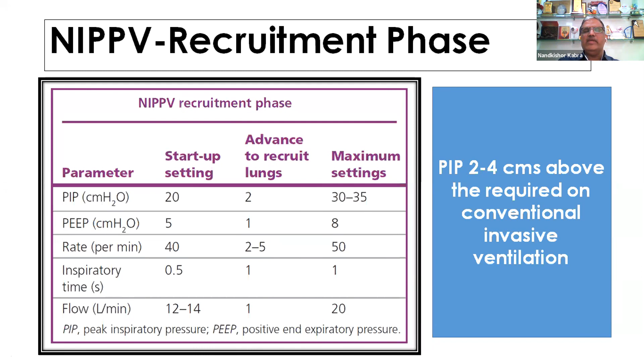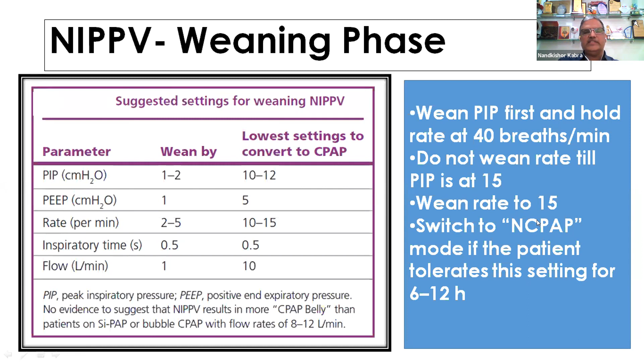It is generally said that you don't have to worry about this higher pressure, because when the pressure reaches the pharynx, the levels of pressure start to fall, and when it reaches the alveoli, it is even lower because you are having variable leaks at many places. When you wean, you would wean the PIP first, and you would not touch the rate. Once the PIP comes to something like 15, then you would start reducing the rate. And once you have reduced the rate to 15, then you may switch to CPAP if they are stable for about, say, 6 to 12 hours.